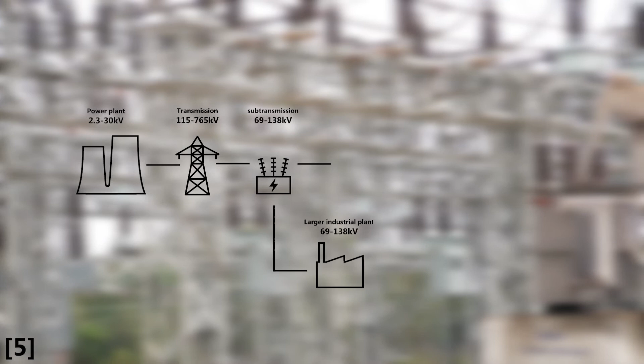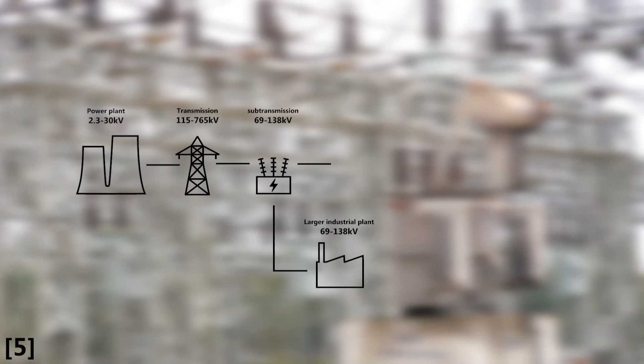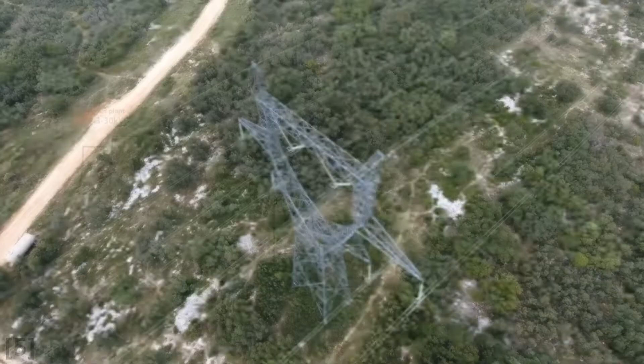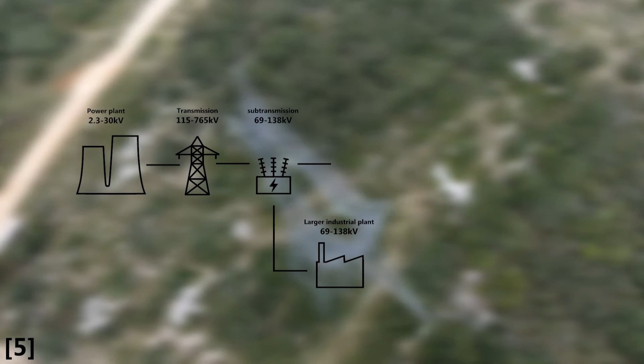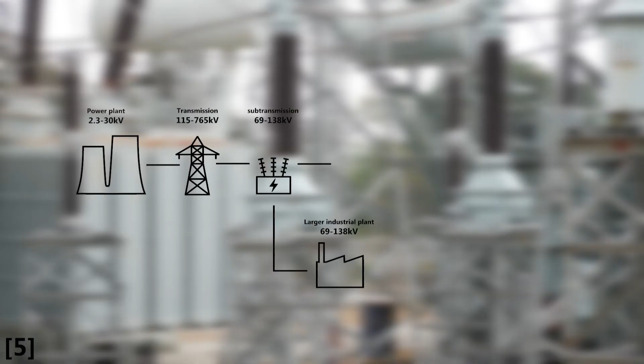This happens in multiple stages due to the costly equipment needed to step down high voltage. The first stage is subtransmission, where high voltage is stepped down to 69 to 138 kilovolts. HVDC will also be converted to alternating current at this stage. While high voltage is used to transport energy from point to point, subtransmission serves an area which may be used to directly power larger industrial plants.